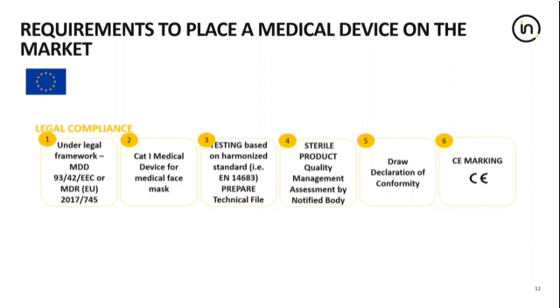And a CE mark can be applied and does not require the involvement of a notified body to certify unless the face mask is a sterile device. And if it is a sterile device, a notified body certification should be included from a medical devices notified body. The importer should hold the technical file, or they may have an authorised representative located in Europe to hold the technical documentation. And they can prepare a declaration of conformity, which includes the name of the importer or authorised representative. And finally, a medical device should be registered with the appropriate medical body for approval to be used.